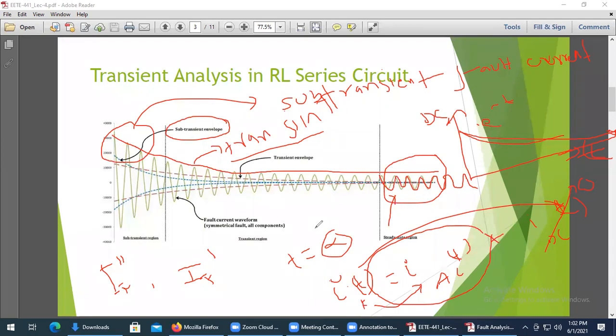But in practice, let me clear up one thing. This steady state period will be achieved if you allow the fault current to flow for a very long period of time, but in a practical scenario we don't get that. Why? Because, like I said before, in the power system not a single point is unprotected. Every item, component or point should be protected by a protective device, normally a circuit breaker, though in lower voltage systems sometimes we use a fuse. These devices operate very quickly, because we cannot let fault current flow for a long time. The magnitude of the fault current is generally higher than the nominal current rating, so the higher the fault current, the greater the probability of damage to your appliances, equipment or the whole power system.